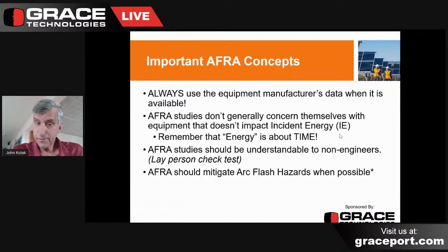Now, the next point is also very important, and that is, remember, when we talk about the term energy, we're always talking about an element of time. So in terms of incident energy, there are two things to concern ourselves with: the magnitude of short circuit current that's being released in the system, and the arc duration. How long does it take to actually clear the arc, the faulted element, from the system? So when we talk about incident energy, the magic number that appears in the regulations is 1.2 calories of heat per square centimeter of your skin. So it's heat per unit area.